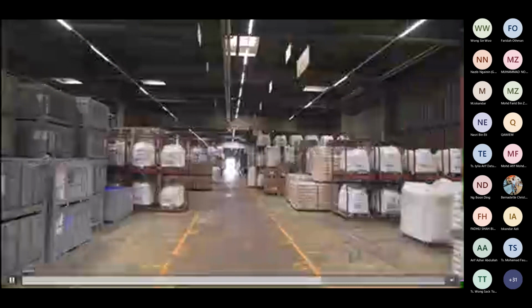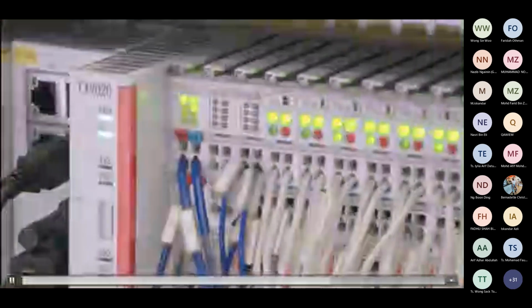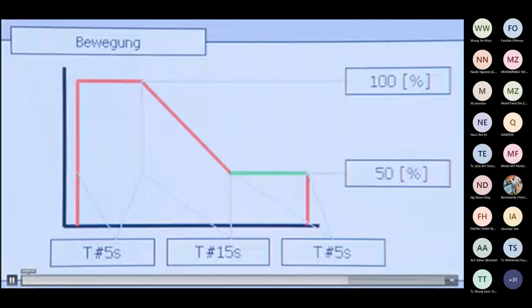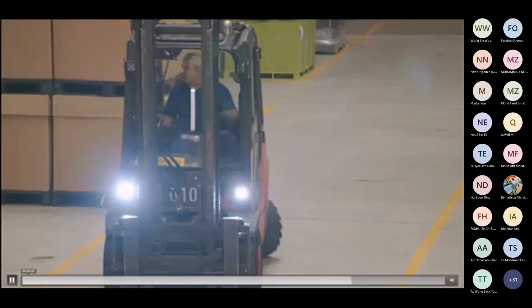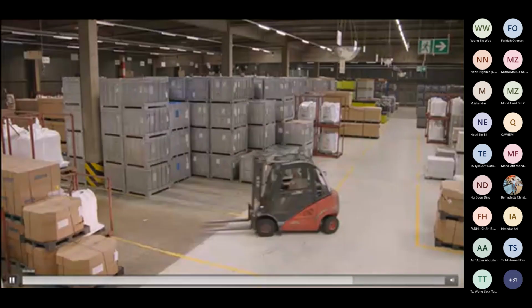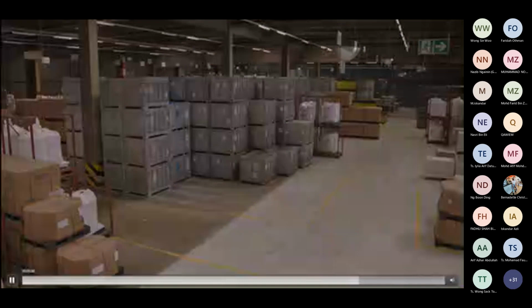The system knows all the driving and walking routes. As a result, neighboring areas can already be slightly dimmed and only stay on for a preset time once the area has been vacated. Passageways are always set at the minimum level. This translates to a savings from 20 kilowatts, which is what we were using with the old lighting system, down to a final 1.5 kilowatts. That's an enormous reduction, a bit more than 90%, that we are now saving here.